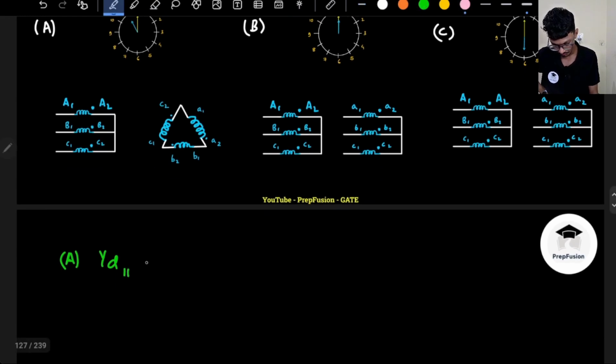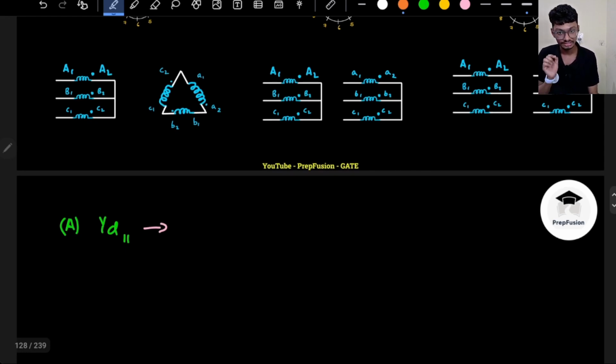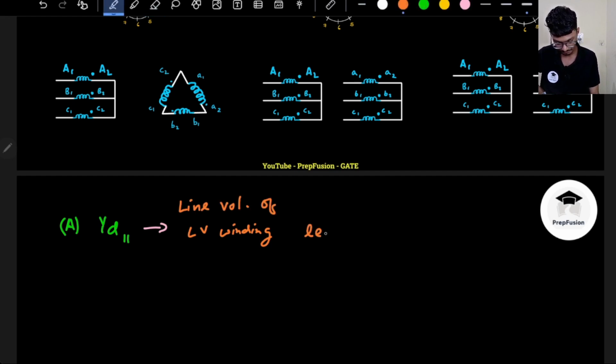Okay, so what I can comment is that if it is YD11, that means the line voltage of the LV winding leads the line voltage of the HV winding.